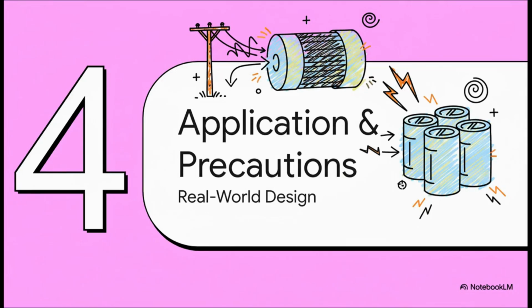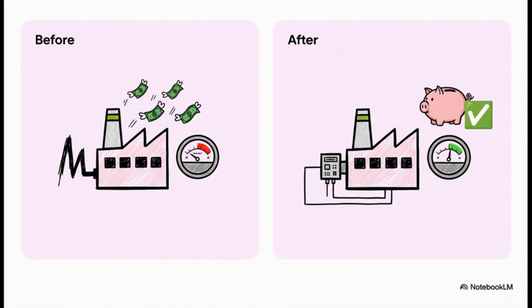Okay, let's put all this theory into practice. We're going to look at a real-world scenario, and then we'll cover some critical precautions you absolutely have to consider when you're designing one of these systems. Check out the impact here. It's pretty amazing. We have a factory that was running at a pretty poor power factor of 0.78, and they were getting hammered with penalties every single month. After they installed a correctly sized automatic capacitor bank, they boosted their power factor all the way up to a solid 0.96. And the results? They speak for themselves. Lower current draw, no more penalties, and a lot less stress on their expensive transformer. That is a tangible, real-world win.